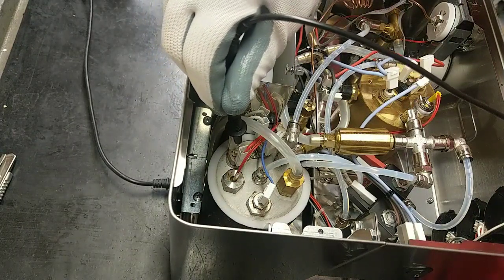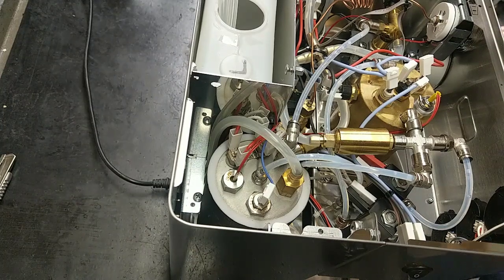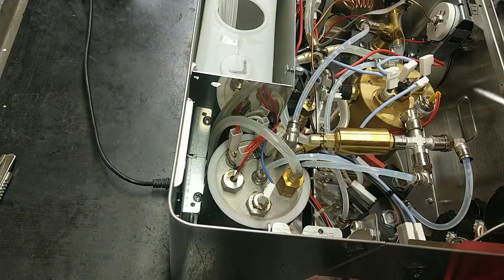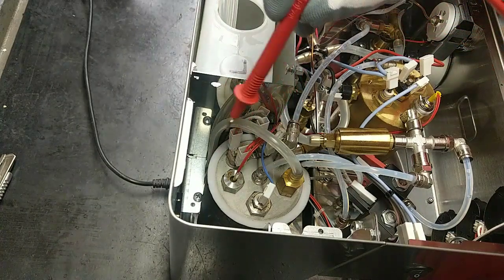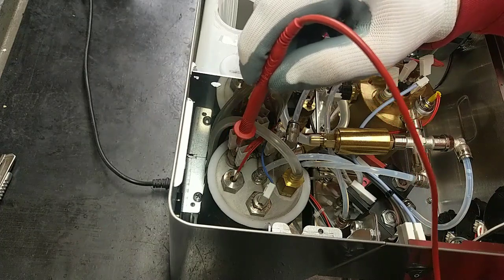Okay, I checked this safety thermostat, and I heard a click. Now I have to see if this works, because probably it is only the safety thermostat. Click. Heard. Both of these two safety thermostats worked. Then cut the power. The problem was this, and this.